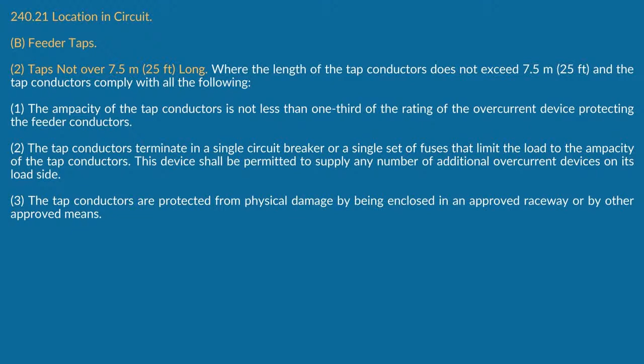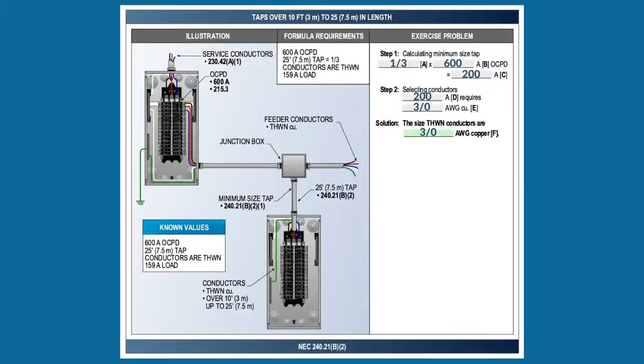I go over and I look at table 310.16. A 3/0's good for 200 amps on the 75-degree C terminals. You just saw it too. Yeah. Bijan's going to be a stud, I think. But anyway, if you look at that, as I was saying, anything 10 foot or less, divide by 10. Everything else, I take it what? 1/3. Okay. Here you go. These are the rules. You got a 3/0 conductor. In that case, that means 3/0 is the smallest conductor, and I'd have to have a 200 amp overcurrent device there. Okay.